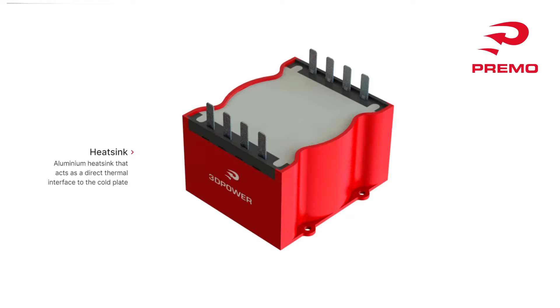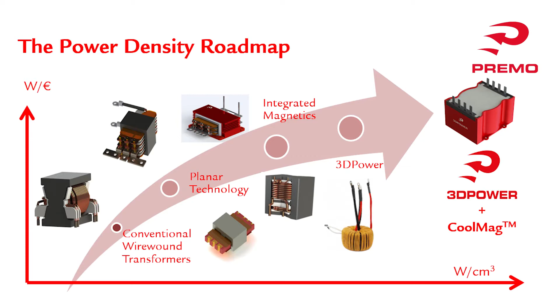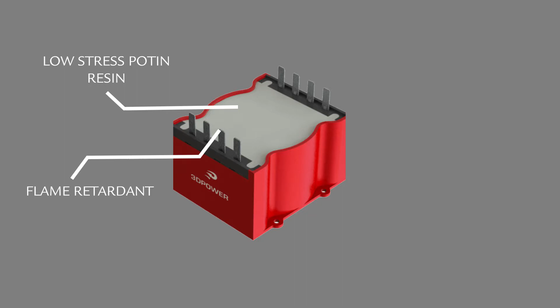When we design power densities and sizes over 7 kilowatts, the amount of heat increases, as I explained, and we have to use a potting compound to help dissipate heat from the top of the magnetic to the liquid cooling plate on the bottom. To achieve this we use this gray compound you see here, a specific custom developed silicone compound made 100% focused on magnetics for power electronics.